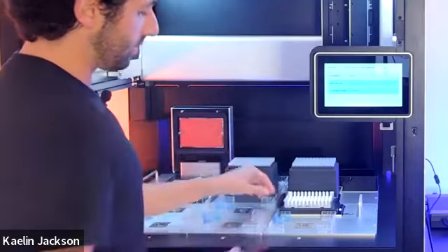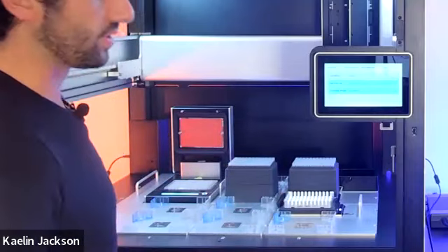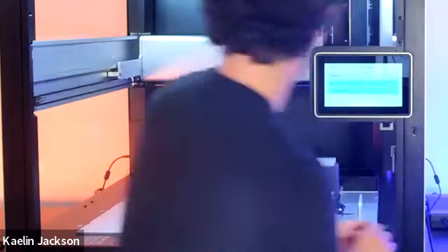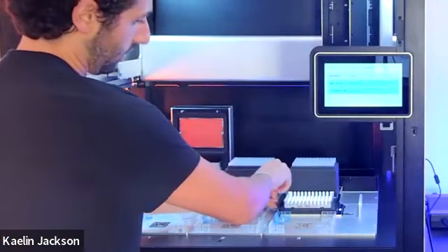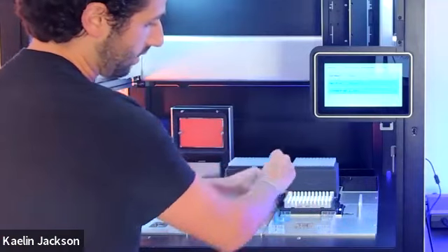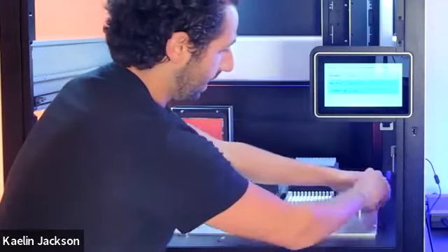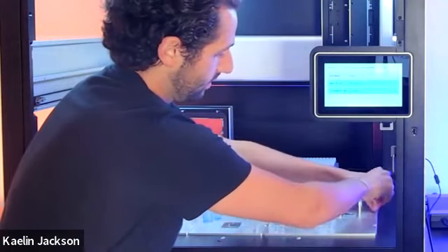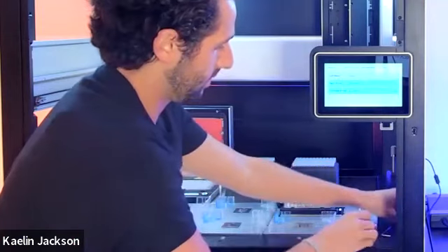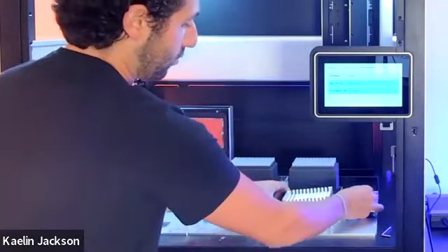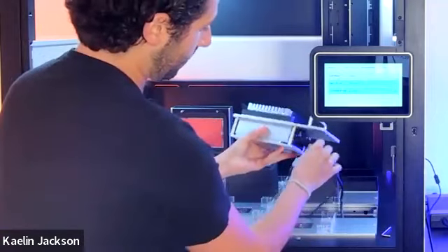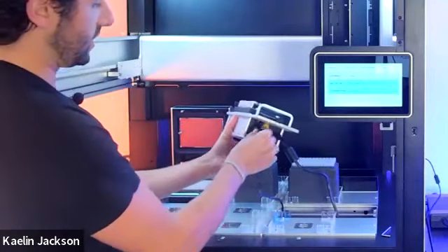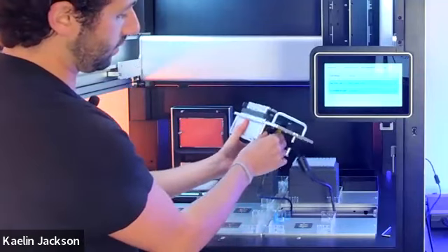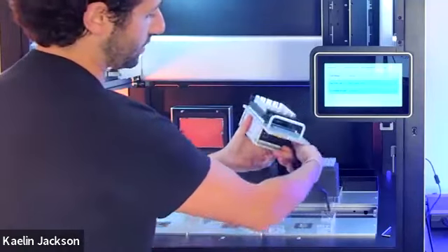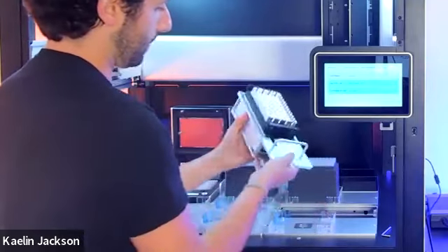So it's quite simple to replace the heater shaker in this case. I'm going to use a 3 millimeter wrench and simply pop out the 2 screws holding the slot and carriage in place. And once I physically remove the module from its position, you'll notice there are 2 connections, one of which is a USB connection, which allows the robot to speak with the module. And the other is the power source for the module. I'll place that to the side.